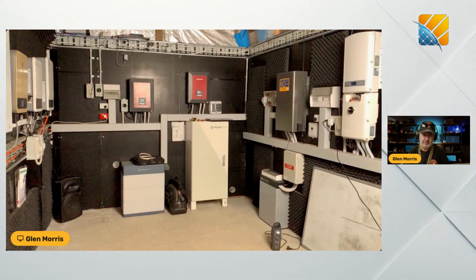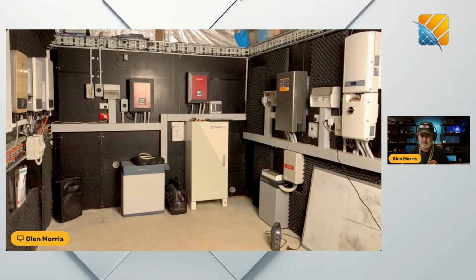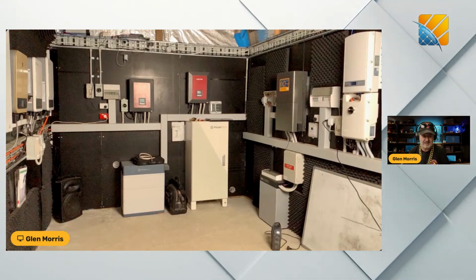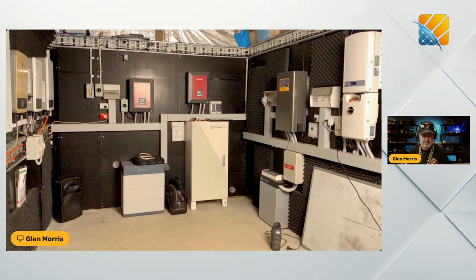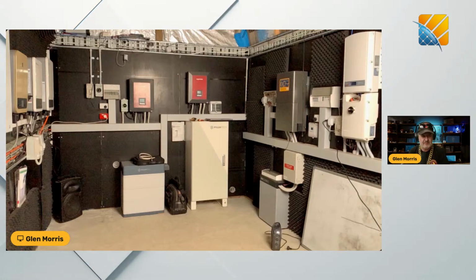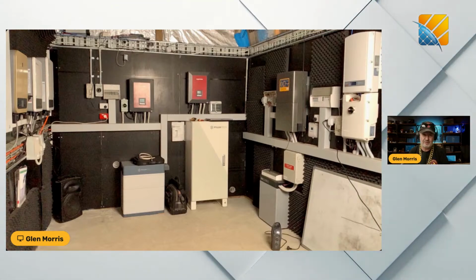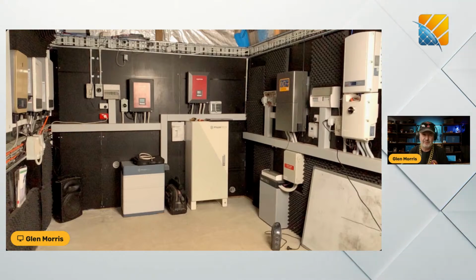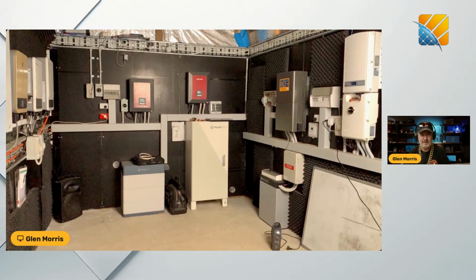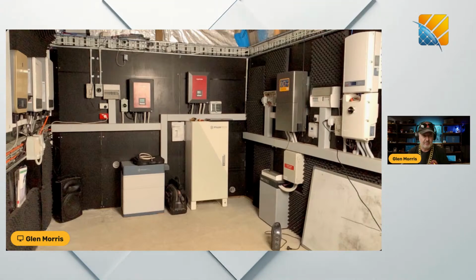What we've done here is get 2 different battery systems. We've been doing R&D work with Pylontech and Ingeteam, integrating different systems together. On the left-hand side is the Pylontech Force H1, their stackable modules. You can have more than 3; here we've got 3 modules. Each time you add another battery in the stack, your voltage goes up. That's one of the advantages of the Ingeteam, it's a high voltage battery input inverter. It can take up to 300 volts on the battery port and as low as 40 volts, though really you want to be above 120 to get full power out, so 120 to 300 volts is where it's at for the battery port.